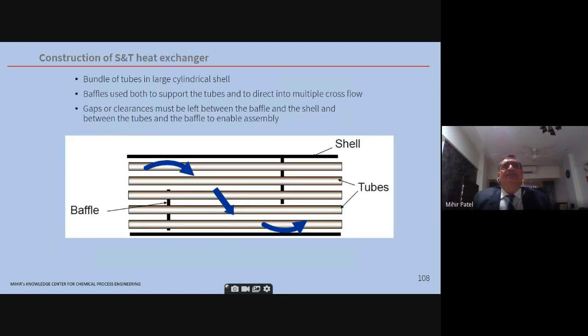Construction of shell and tube heat exchanger. As you can see, the bundles of tubes in a cylindrical shell. Baffles are used to support the tubes. Gaps or clearances must be left amongst the tubes and the inside of the shell, in between the baffle and tubes, etc., for proper construction.